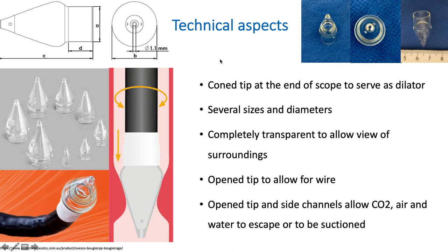What are the technical aspects of the bougie cap? The bougie cap is attached to the distal part of the endoscope so that your endoscope becomes a dilator. The coned tip will dilate different stenosis. There are different types and shapes of bougie caps. This cap is completely transparent, so it allows for a view of the surroundings, and it has an opening tip to allow for passing a guide wire, if needed.